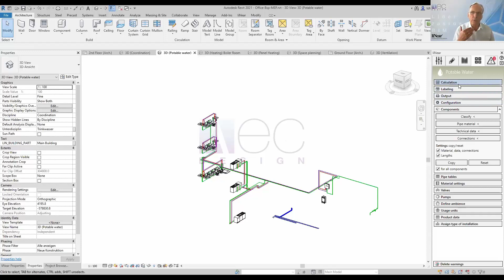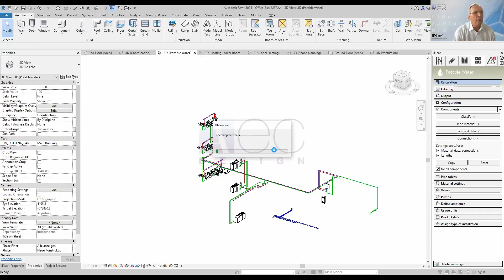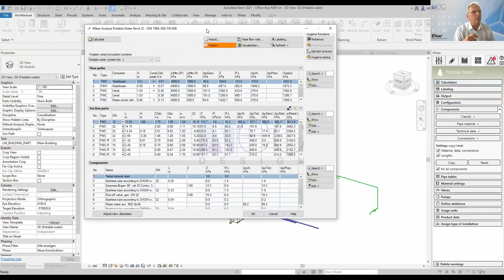I'll show you the whole calculation process, done just by clicking here. The components are detected, the network is checked, and it comes up with a result dialog. The result dialog is organized in a certain way: you see the flow path on top, and within a certain flow path you have sections, and within the sections you have the elements — the real pipes and fittings.